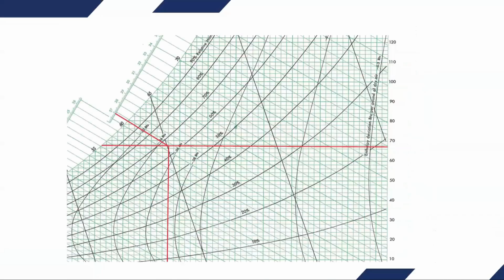This is just a blow up because it's hard to see that psychrometric chart on the first page. But again, you can see that we're running about 68 degrees, 65% relative humidity, which indicates that we've got 68 grains of moisture with a 56-degree wet bulb or dew point.